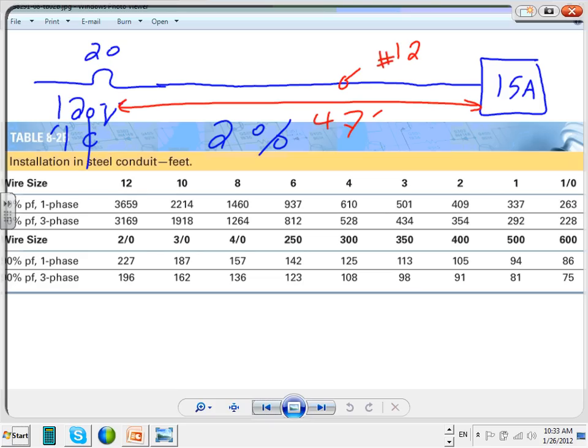That's not a whole lot, is it? 47 feet. I think it's 36, yeah. You good? No, I'm sorry, I should have explained myself. When you use this table, guys, you go by the load. You always go by the load. You do not go by the overcurrent device, because the load is the current that's going to go through the conductor. If my load is 15 amps, I go by the load. So my load is 15 amps, not 20. The load is 15, so I can go 47 feet.